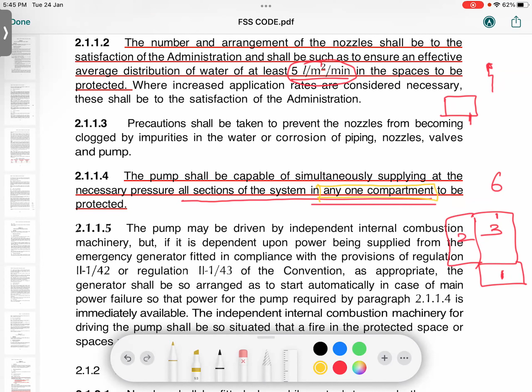The pressure should be there in the pump so that at a time it can supply the water to all the nozzles in the same compartment. Same compartment means in that confined space, right? Like purifier room is separate. Your machinery space is separate, right? Suppose you have some other machinery, that also is separate. If it is in a separate compartment, the pump shall be capable of simultaneously supplying at necessary pressure all sections of system in any one compartment. In any one compartment, right? That is important.